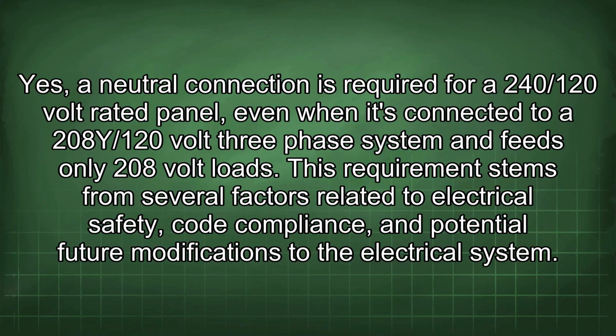Yes, a neutral connection is required for a 240/120 volt rated panel, even when it's connected to a 208Y/120 volt three-phase system and feeds only 208 volt loads. This requirement stems from several factors related to electrical safety, code compliance, and potential future modifications to the electrical system.